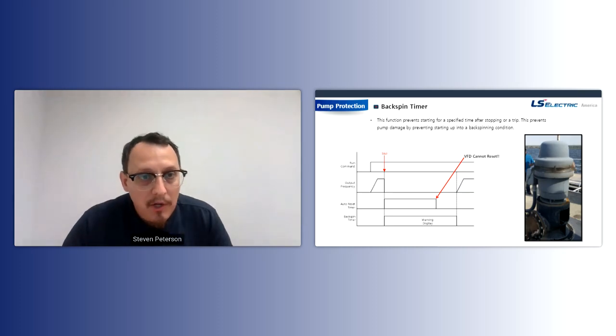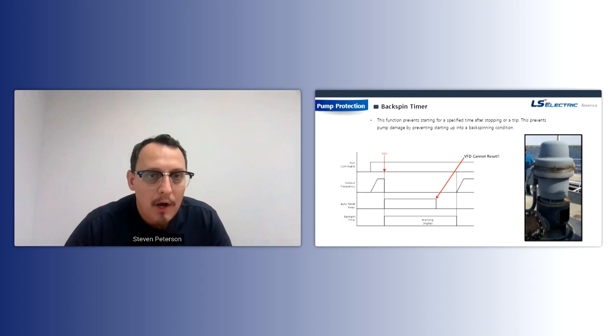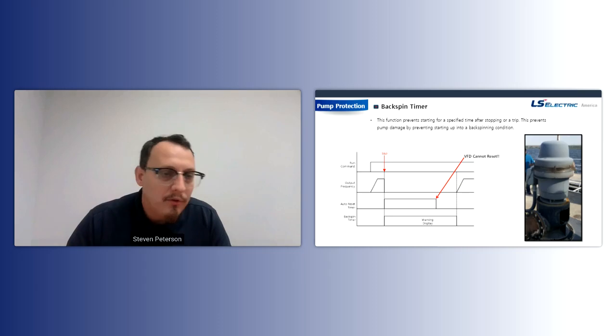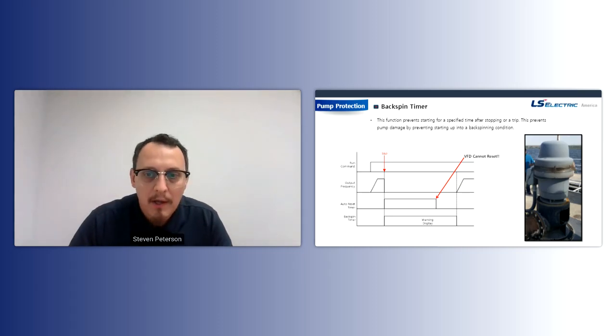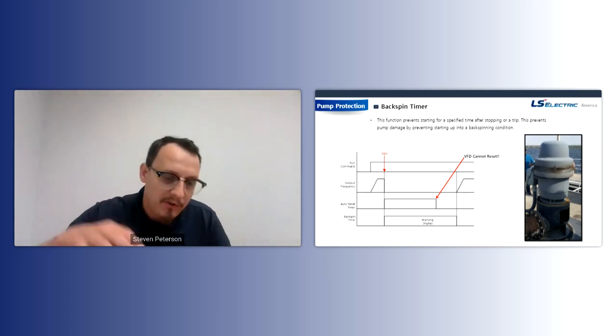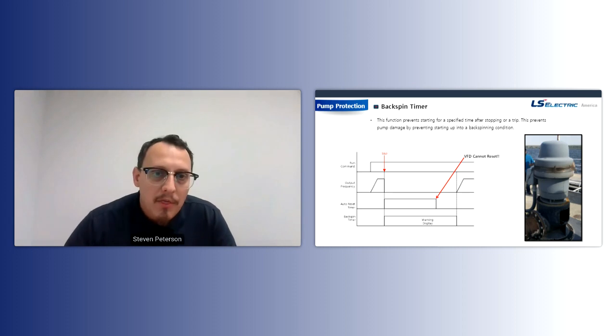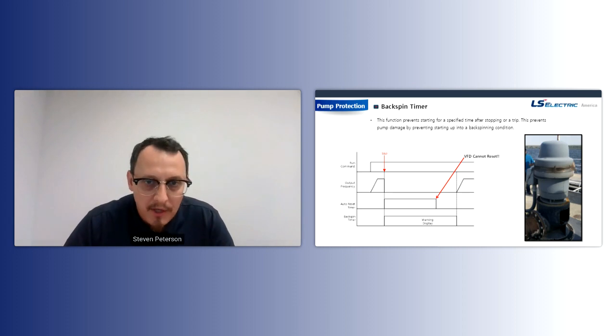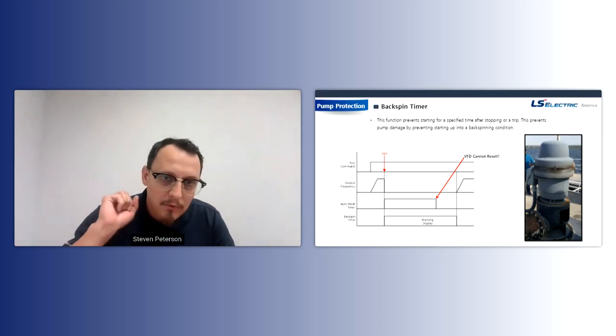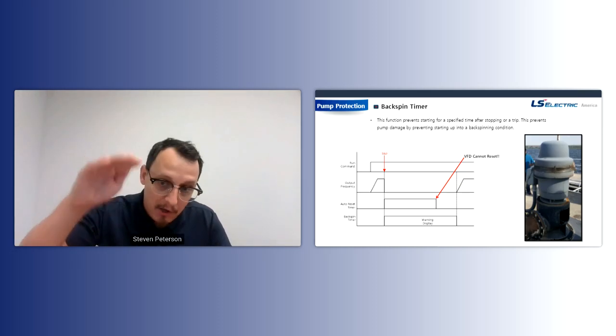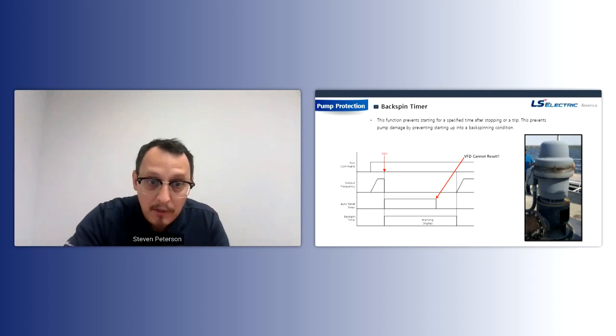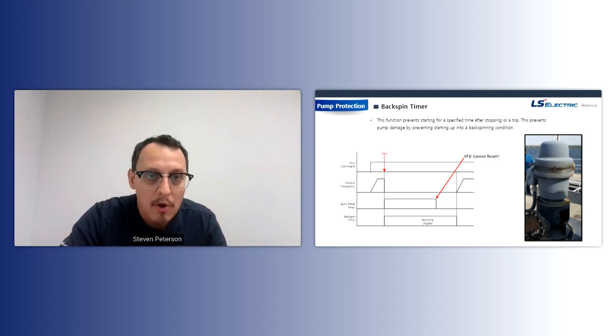Another thing you guys may care about is a backspin timer. Backspin timer is essentially like a run delay. So if you're running a vertical turbine and you stop it or you lose power or something, and the shaft starts backwards and the water column's falling down, you don't want to start into a condition like that. So a backspin timer is exactly as it sounds. You could set it to a very long time based on how high that water column is. It's not going to let the drive run until that timer counts down to 0.